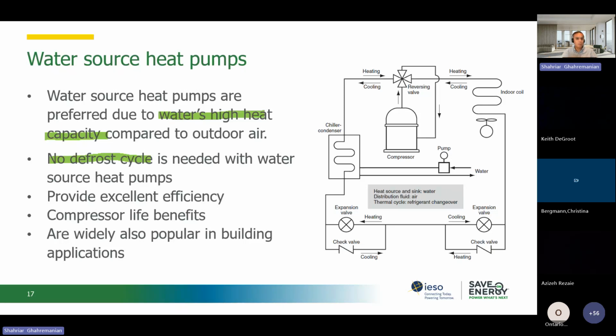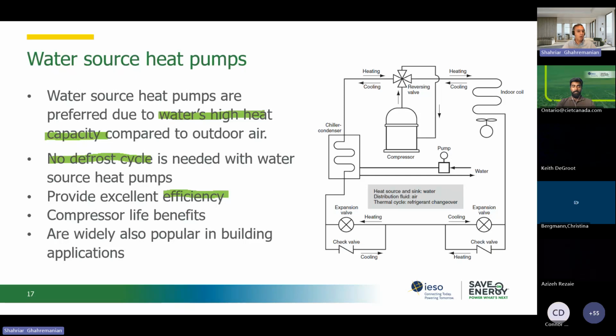So it has higher efficiency. One reason is the high heating capacity of the water. The other one is that there is no defrost cycle and so on. Because of the water, the compressor works less. So it is good in different types of buildings. If your project is nearby water, and for environmental reasons you're allowed to use that water, or you're allowed to connect your heat pump to that, consider this one, and that might be a good solution.